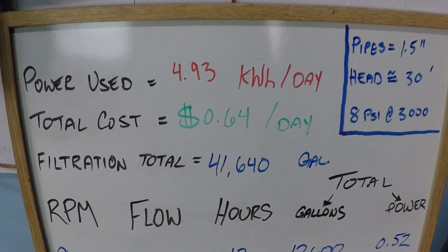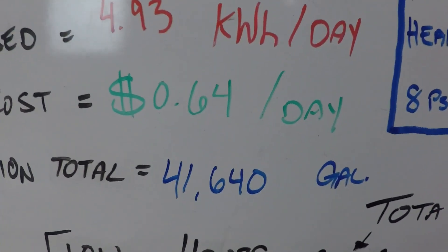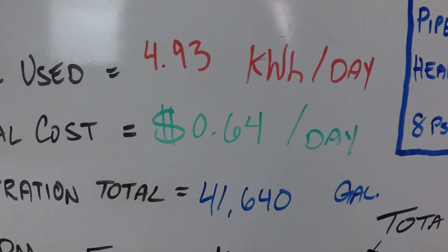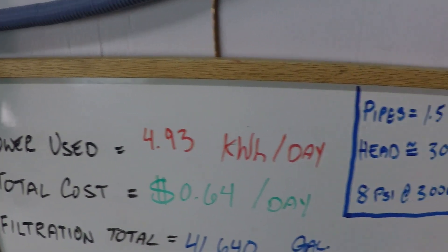Filtration schedule breakdown. This is a 24-hour dynamic variable speed pump schedule where we are going to pump 41,640 gallons of water through the filter. It's going to cost us 64 cents on average using 4.93 kilowatt-hours of power.